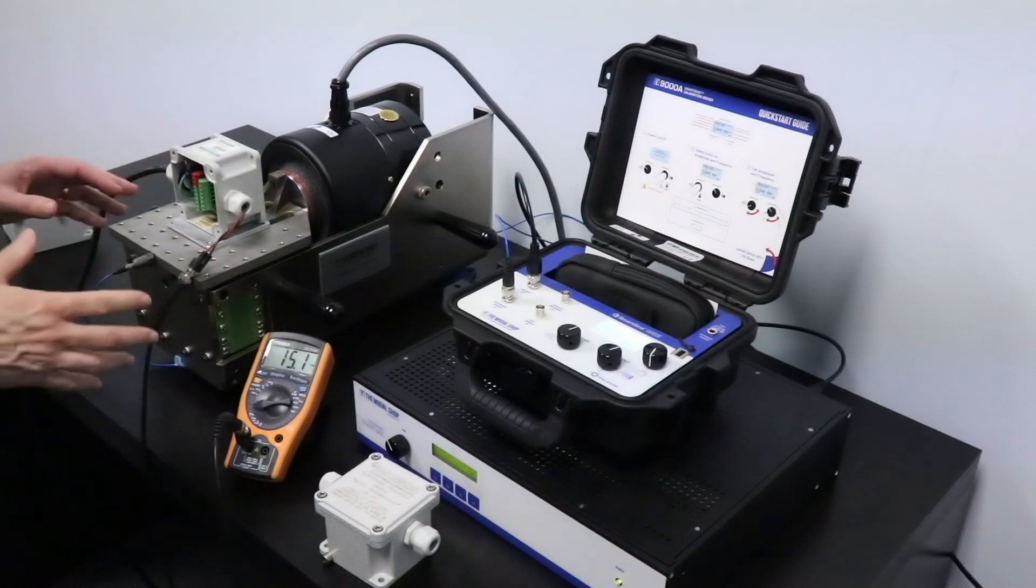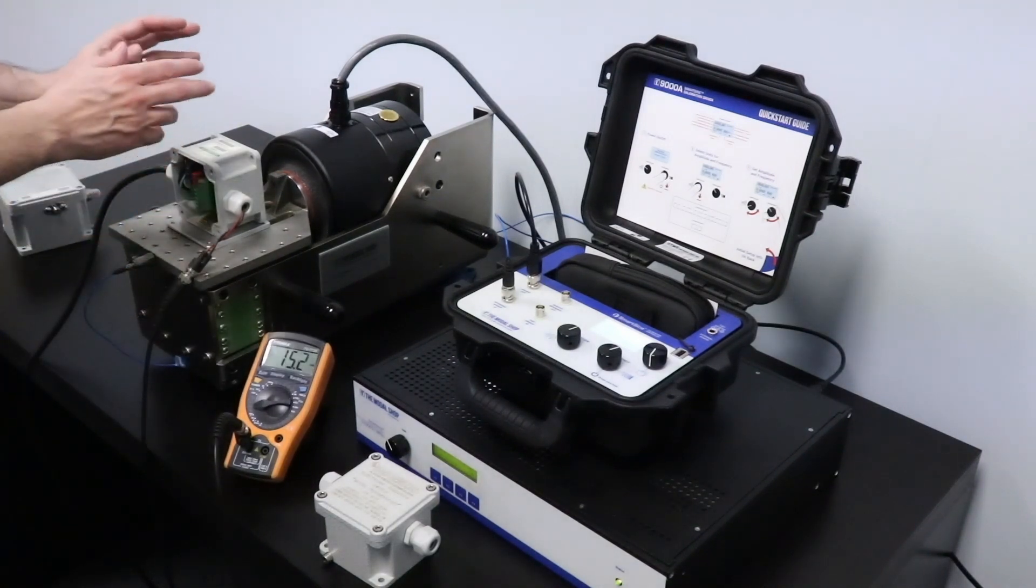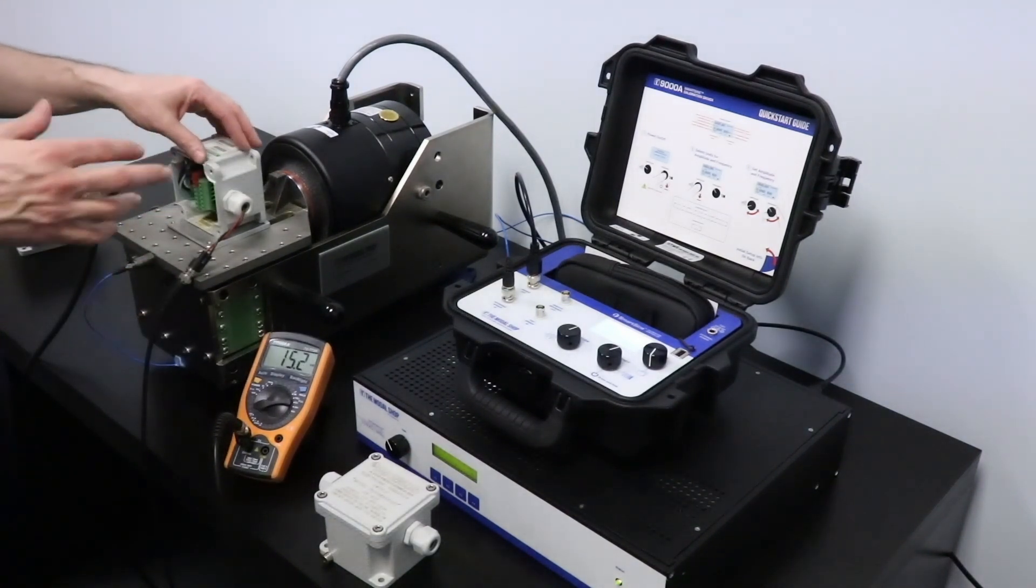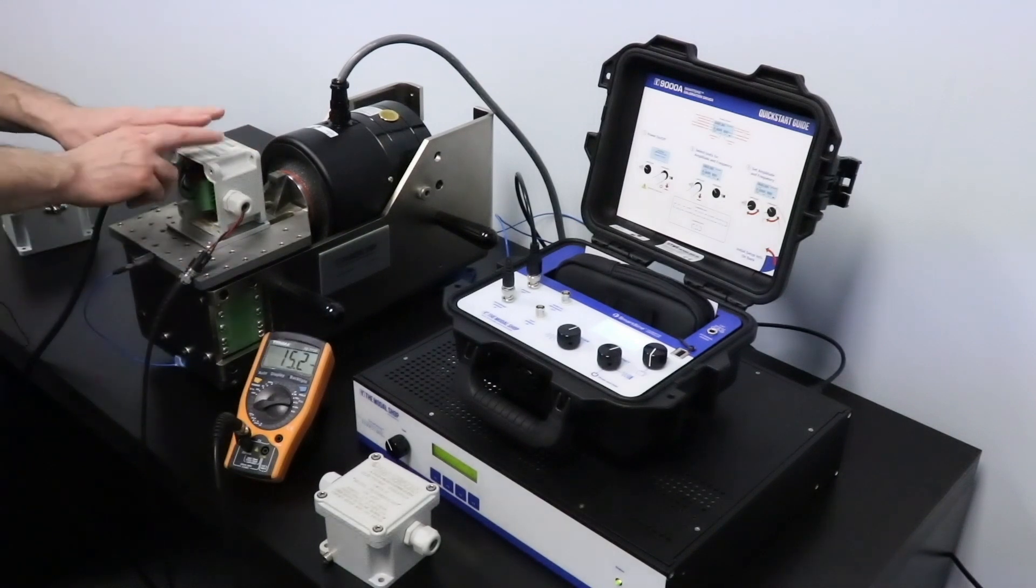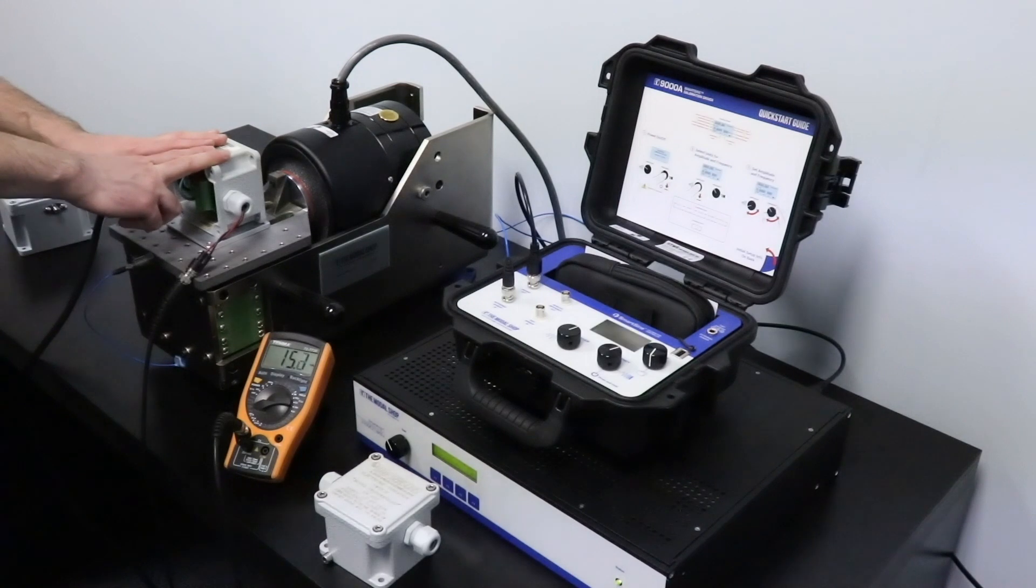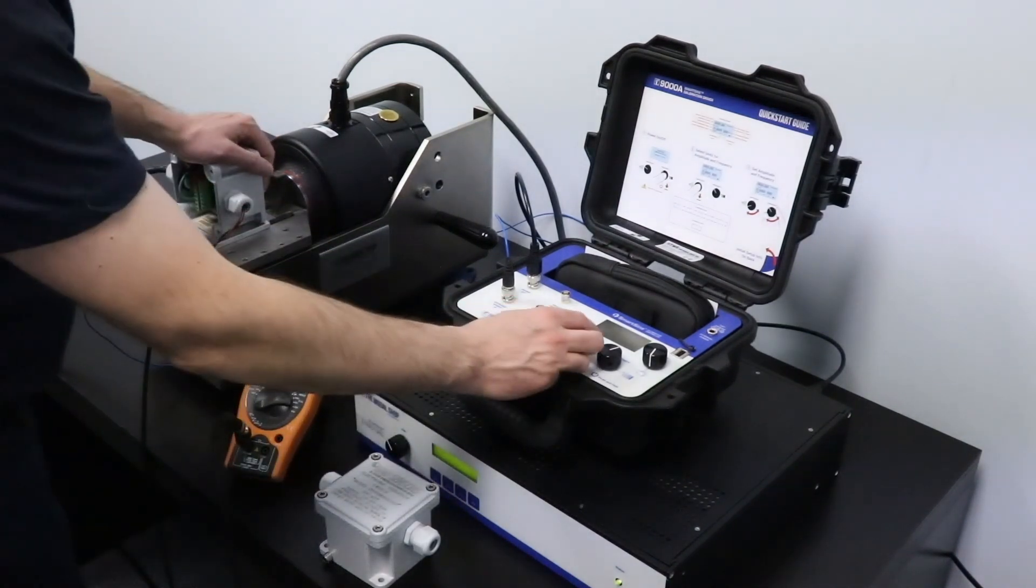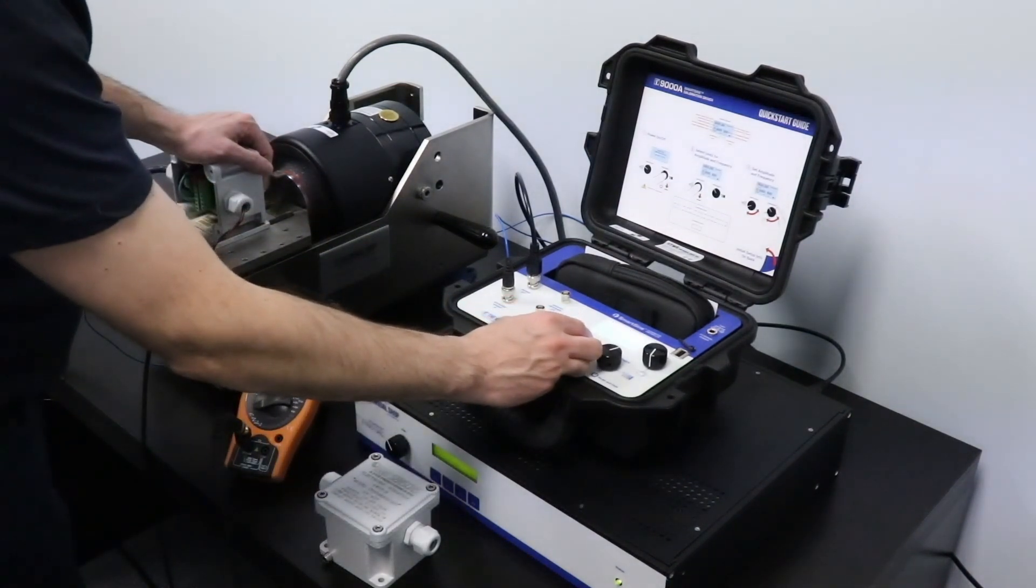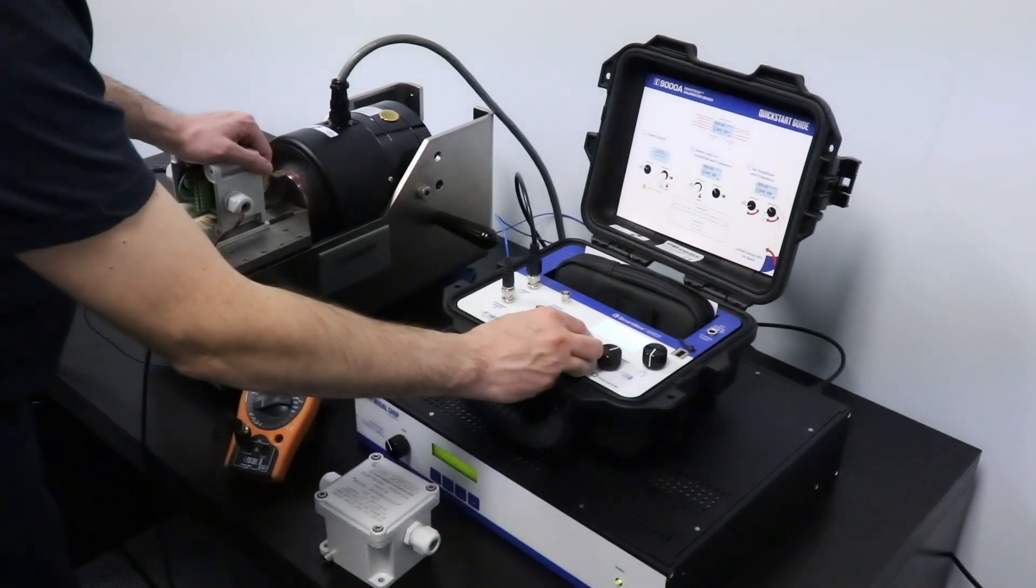So I can test the vibration switch all the way to full scale. So this particular switch is about 1.5 inches per second. So if I dial in 1.5 inches per second on my 9000A, I should get the full scale.